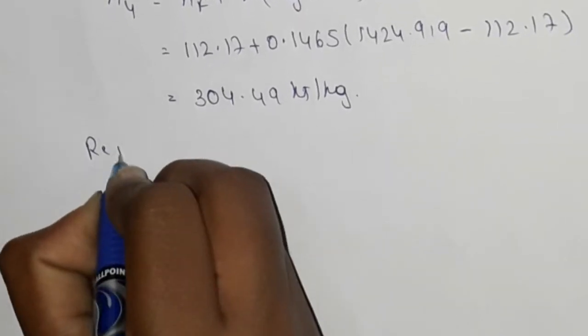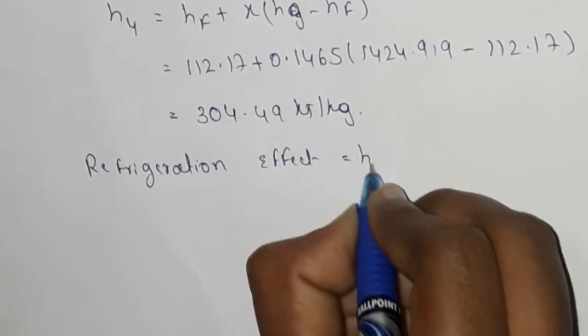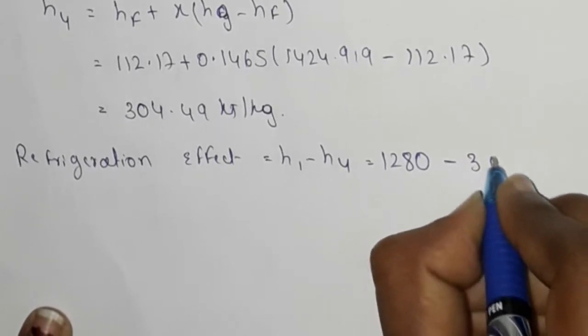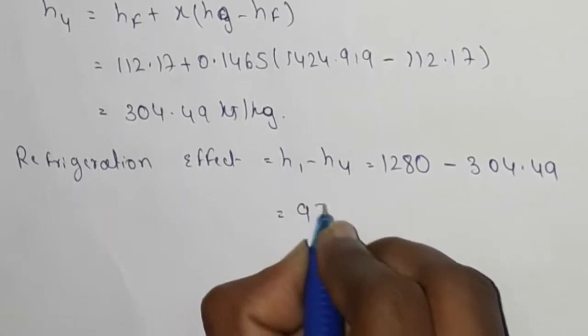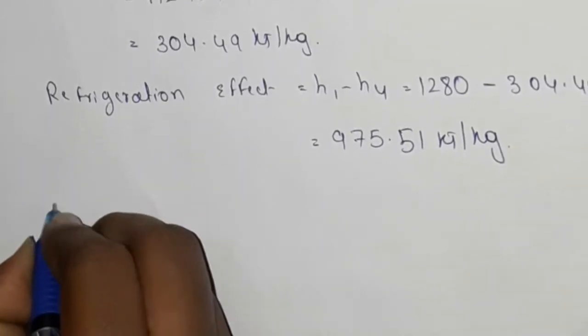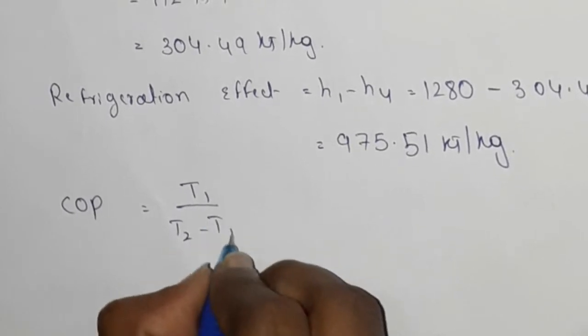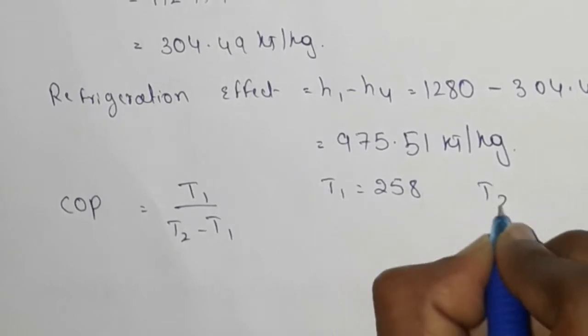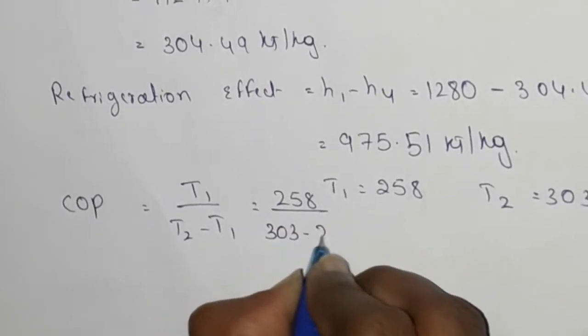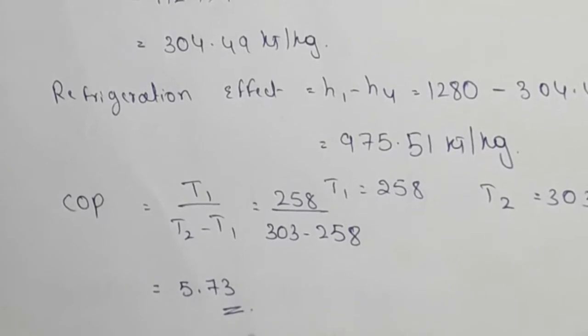The refrigeration effect for the Carnot cycle equals H1 minus H4, which is 1280 minus 304.49, giving 975.51 kilojoules per kg. The COP for the Carnot cycle is T1 divided by (T2 minus T1), where T1 equals 258 and T2 equals 303. So COP equals 258 divided by (303 minus 258), which equals 5.73.